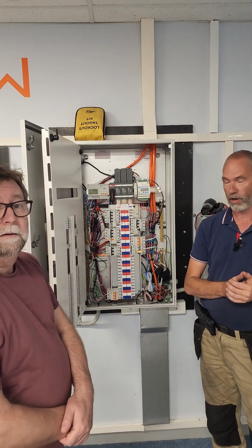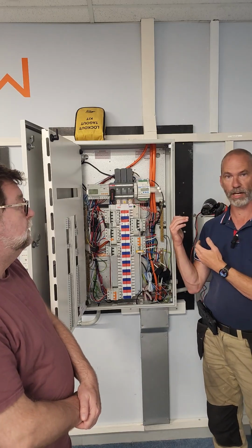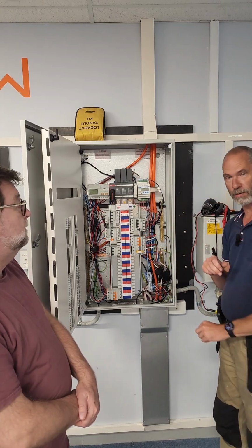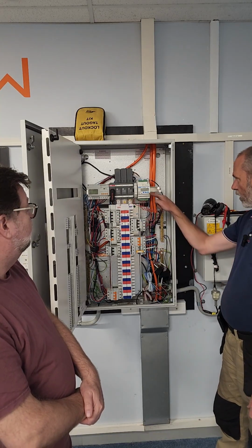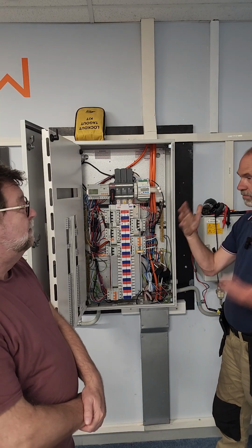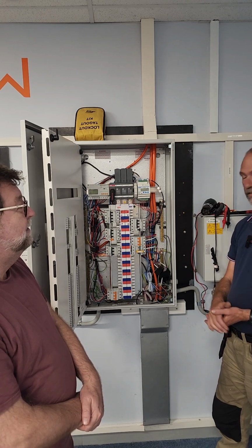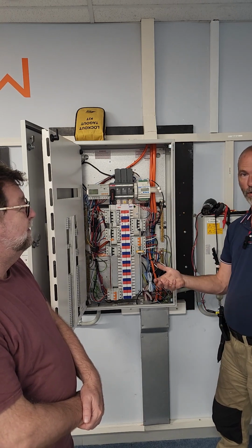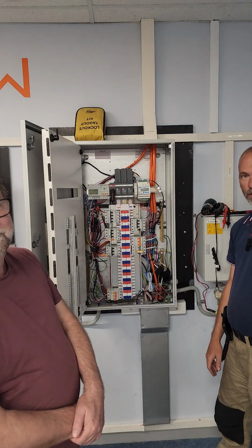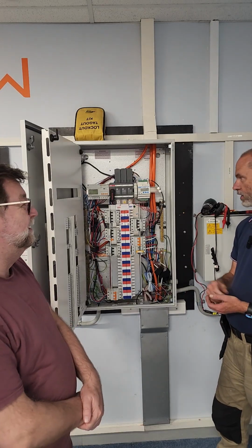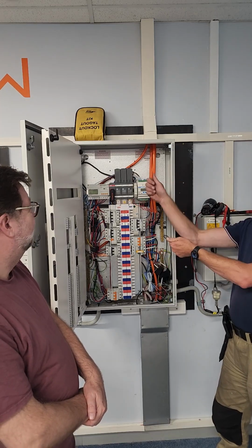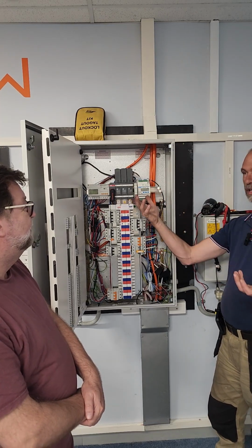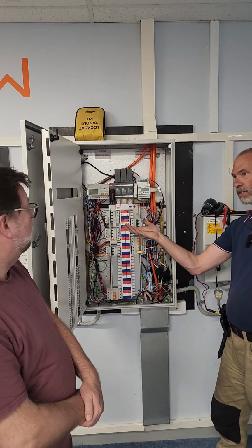Yeah, and obviously if I'm looking at a negative, my CT's flipped. I know I'm checking white phase, so B phase, if it's in the negative, my CT's flipped. If it's 0, it hasn't gone up. Yeah, the phasing's wrong. So even if I'm drawing 6 kilowatts and then I add my 2 kilowatts, if it's not reading 8, yeah, it's in the wrong place.